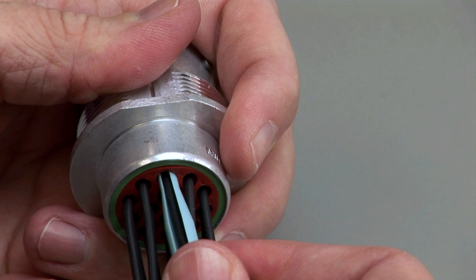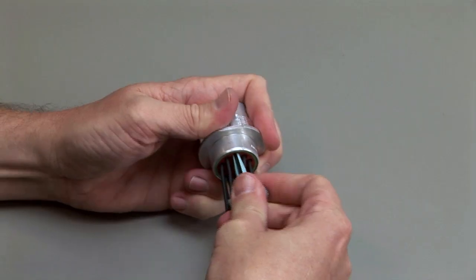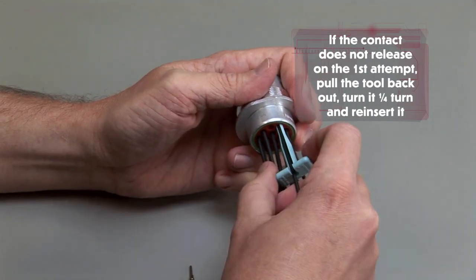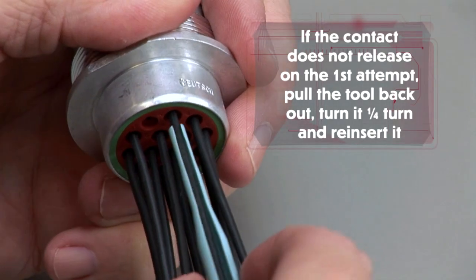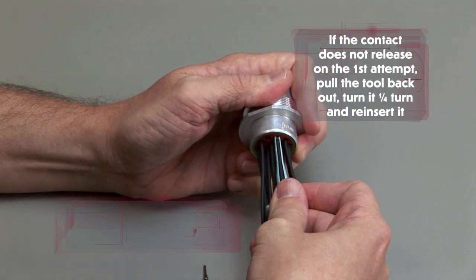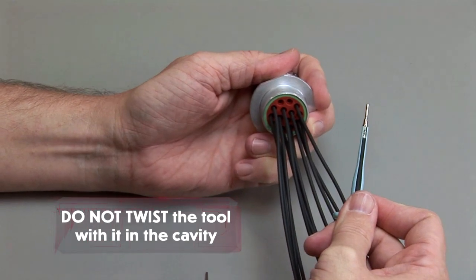Make sure you keep the tool straight and do not twist or angle the removal tool. Pull the contact and wire assembly out of the connector. If the contact does not release on the first attempt, pull the tool back out, turn it one quarter turn and reinsert it. Do not twist the tool with it in the cavity.